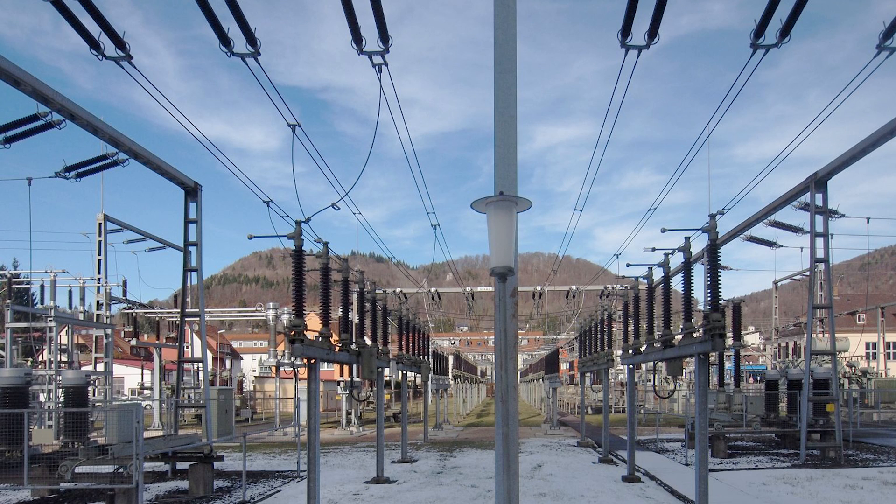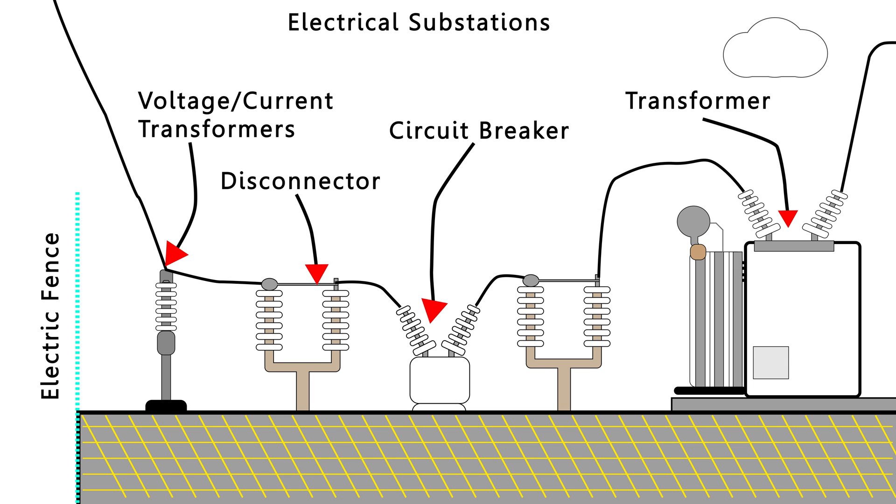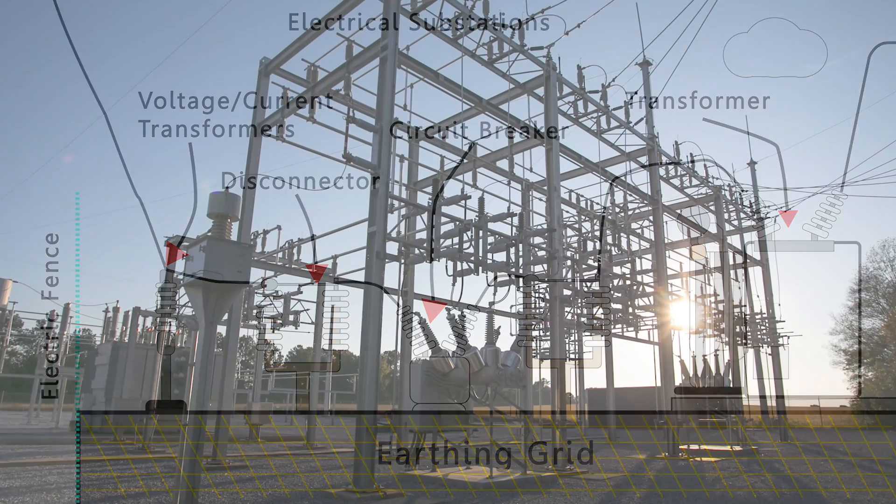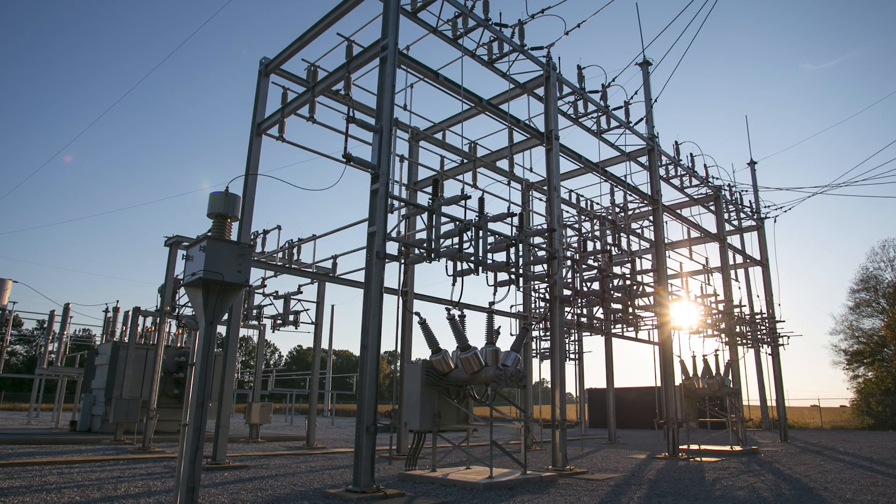Another important aspect of the substation is the earth grid. So underneath the substation you have a grid, a metallic grid, and that helps maintain safe step and touch voltages within the substation to protect personnel from dangerous voltages and to also provide a low impedance path to ground if there's a fault.